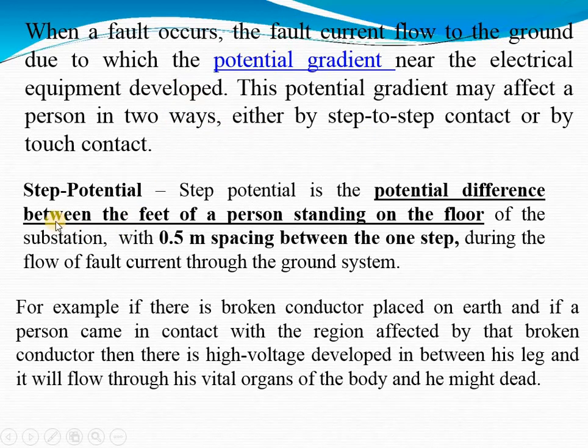Now let's discuss step potential. The step potential is the potential difference between the feet of a person standing on the floor of the substation, with 0.5 meters spacing between each step, during the flow of fault current through the ground system.